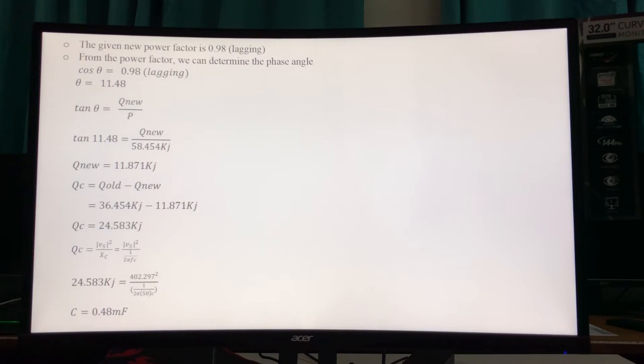The given new power factor is 0.98 lagging. From the power factor, we can determine the phase angle using the cos theta formula, and taking cos inverse theta, we get theta is 11.48 degrees. Using the Pythagoras theorem, tan theta equals Q new over P, we get 11.871 kilo.